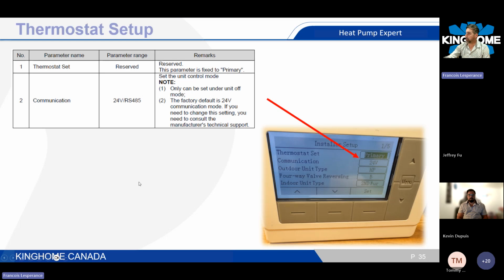Even if you're working from the mechanical room, on the white thermostat, there are two installer settings here that don't appear on the touchscreen controller. The thermostat set over here needs to be set to primary, and the communication that we use is 24 volt. So you don't have to change those settings. They are like this by default, and they have to stay like this.